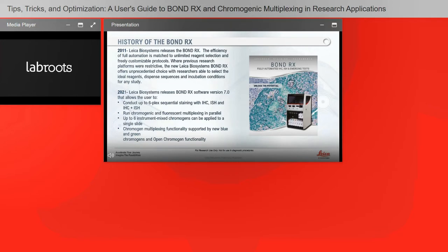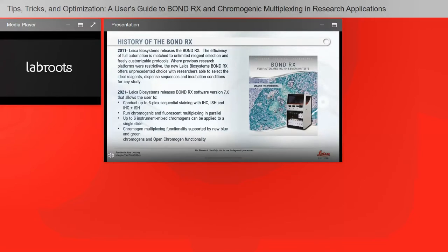In 2011, Leica Biosystems released the Bond RX, where the efficiency of full automation is matched with unlimited reagent selection and freely customizable protocols. You can use any reagent you'd like and develop any type of protocol that you've developed on the bench. The previous Bond 3 from Leica Biosystems was very restrictive, but the Bond RX offers unprecedented choice — researchers can select ideal reagents, dispense sequences, and incubation conditions for a study. Just last year in 2021, Leica Biosystems released Bond RX software version 7.0, which allows up to a six-plex sequential staining.